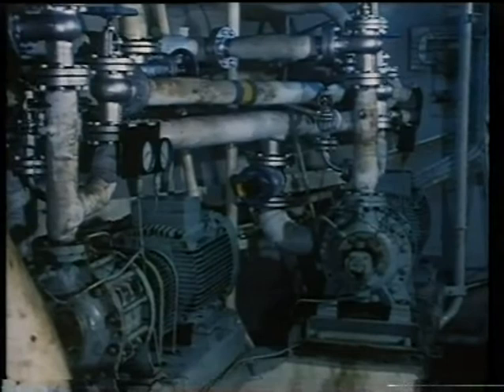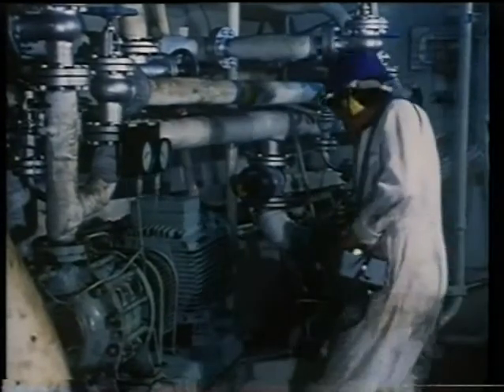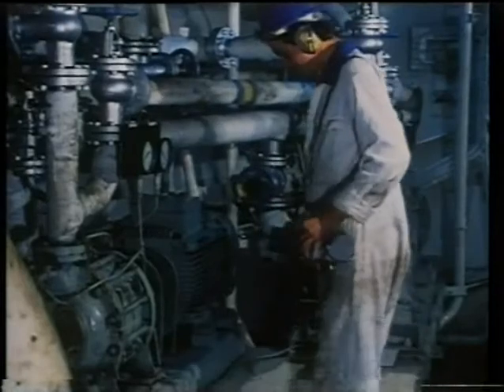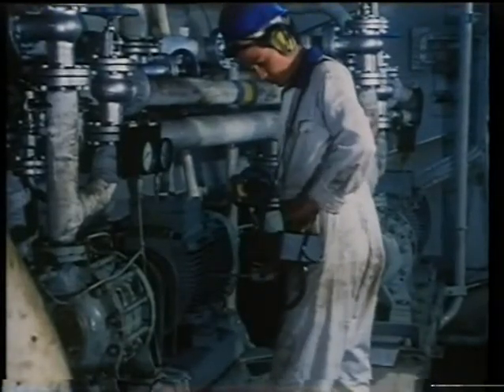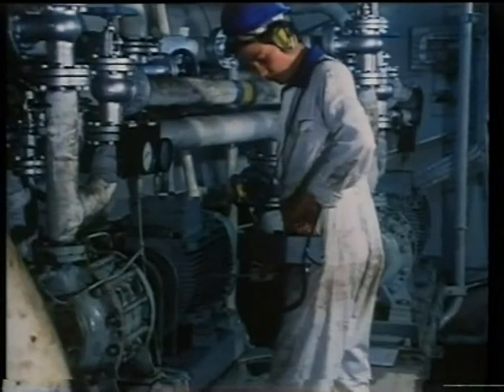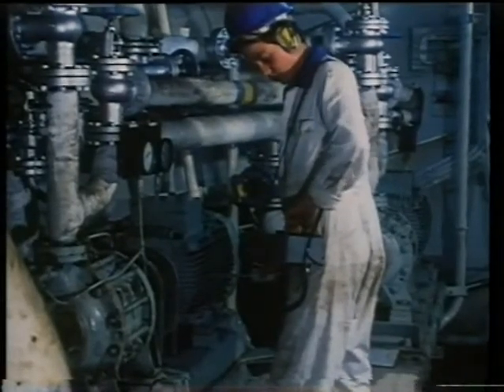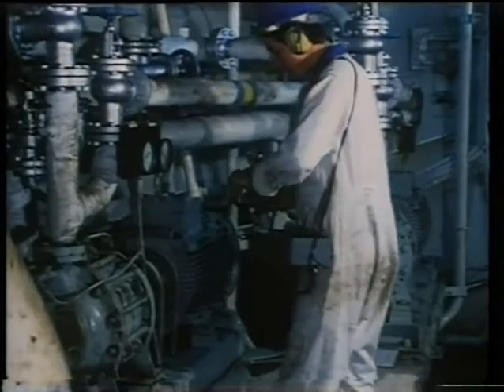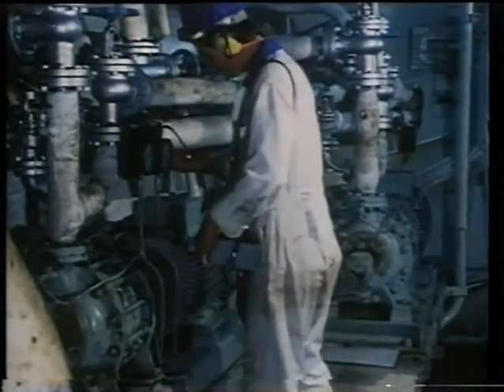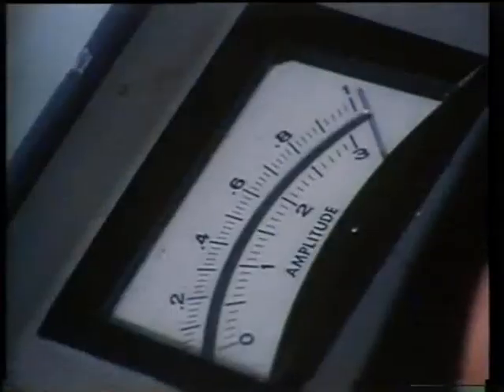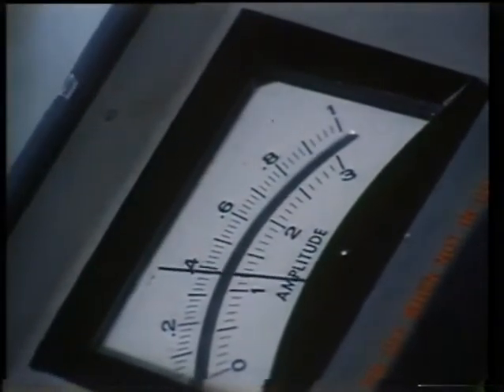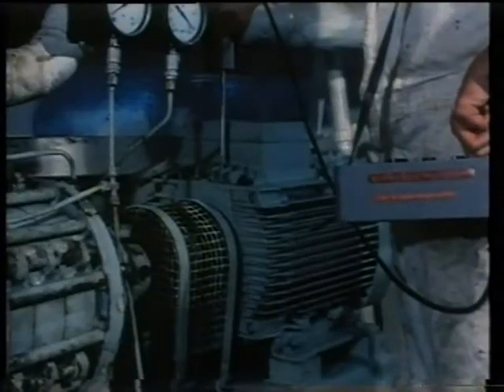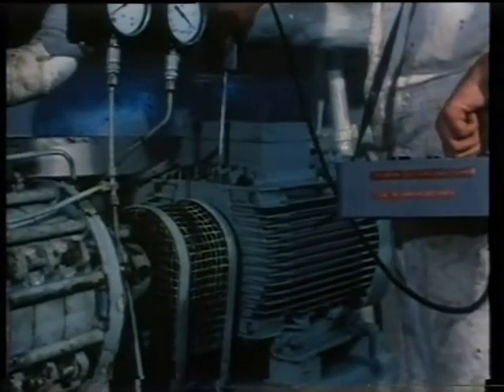The electrical plant and circuitry installed on board ship are subject to wear, tear, and aging. They operate in an environment in which there are great changes of temperature, humidity, salt level in the moisture of the atmosphere, and vibration. They do need constant condition monitoring and maintenance. Preventive maintenance, based on time schedule, was a frequent method of avoiding costly breakdowns. Some chief engineers and electrical superintendents favour preventive maintenance based on insulation resistance trends and vibration monitoring to guide their maintenance planning.